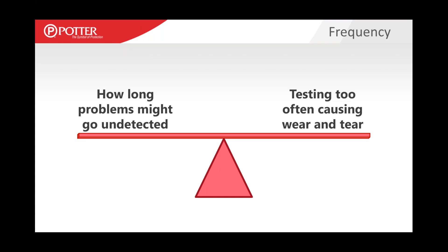So we've identified the issues and how often we should do inspection, testing, and maintenance. The next question is who's responsible for having the inspection, testing, and maintenance done and complying with NFPA 25. Well, this is one of the cases where the standard's actually very clear. NFPA 25, in section 4.1, which is aptly titled Responsibility of the Property Owner or Designated Representative, makes it clear that the owner or their designated representative is the one responsible for inspecting, testing, and maintaining their system. Now, the owner can certainly delegate that authority to an occupant, a property manager, a lessee, or a tenant, things like that. There's some annex material that addresses some of these, and you would expect to see that clarified in an agreement somehow. But ultimately, it's the owner, and that's what we always say about NFPA 25. This is an owner's document. It's the owner's manual for the sprinkler system.